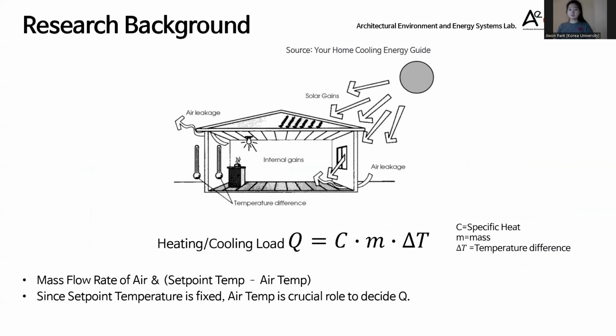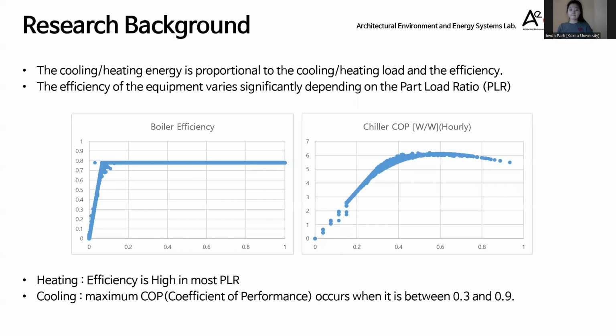A building's heating and cooling load is determined by a simple thermodynamic equation involving the mass of indoor air and the temperature difference between indoor and outdoor air. Assuming that the indoor air is maintained at the set point temperature, the outside air temperature has a crucial impact on the indoor cooling load. Building heating and cooling energy refers to the amount of energy required to meet the heating and cooling load of a building. It is proportional to the heating and cooling load, but also heavily depends on the efficiency of the equipment.